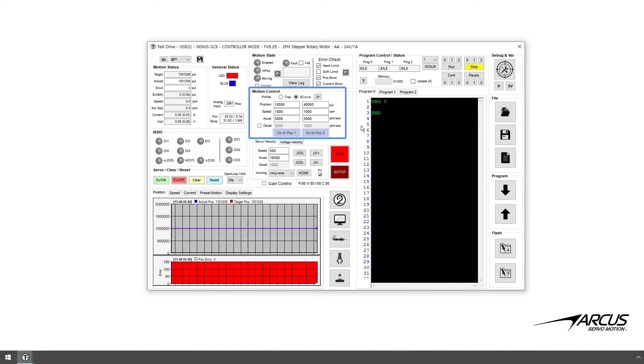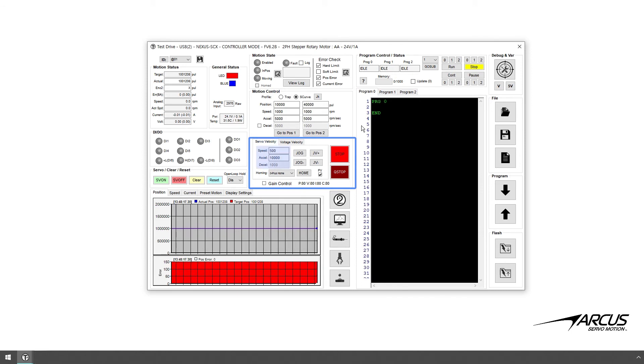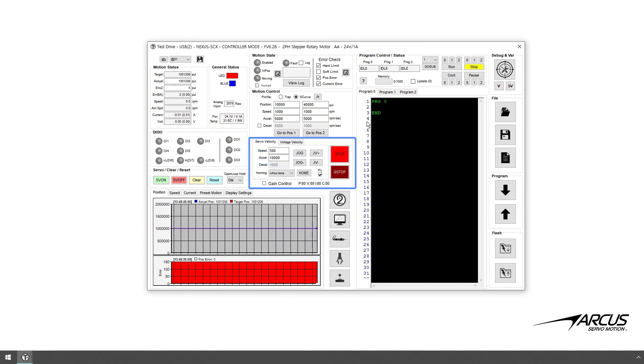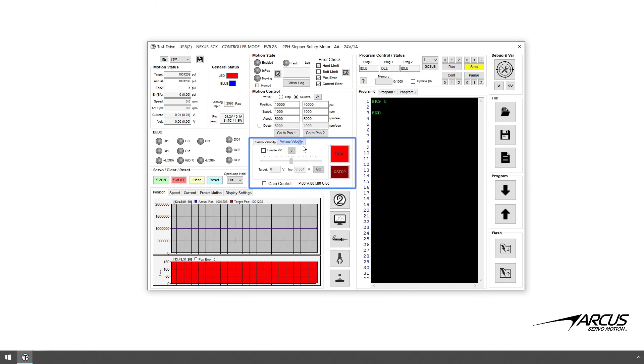Below the target position moves there are two velocity mode tabs. The first is the servo velocity tab — in this tab you can perform constant speed jog and home motions. There are speed, acceleration, and deceleration values used in the constant speed velocity motion. For homing, various mode settings are available. The checkbox next to the home button is the position and velocity servo control checkbox — when enabled in velocity mode, both position and velocity control are performed; if not set, only velocity control is done.